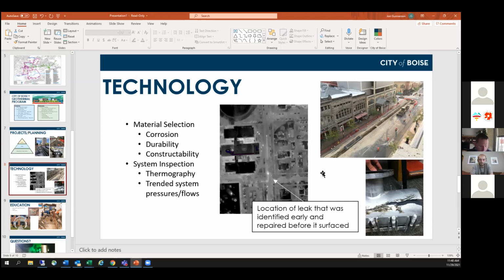Going back to material science class, the corrosivity curve of carbon steel has a bell curve shape, and the top of that bell curve is about 180 degrees Fahrenheit, right at the temperature of our geothermal water. If our water were colder or hotter, things would corrode at a lesser rate, but we're right at that apex, so we see corrosion happening very fast.